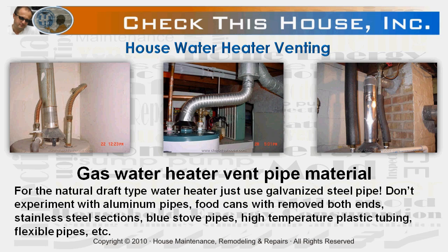Now let's talk about the second component of the water heater venting system: the vent pipe itself. For the natural draft water heater, you should be using galvanized steel pipe only. Do not experiment with aluminum pipes, food cans with removed both ends, stainless steel sections, blue stove pipes, high temperature plastic tubing, flexible pipes, etc. Also, make the vent pipe section between the water heater and the chimney as short and as straight as possible. The common rule is that the horizontal part of the single wall vent pipe must be equal to or shorter than 75% of its total developed height. Check my post for a picture explaining it.